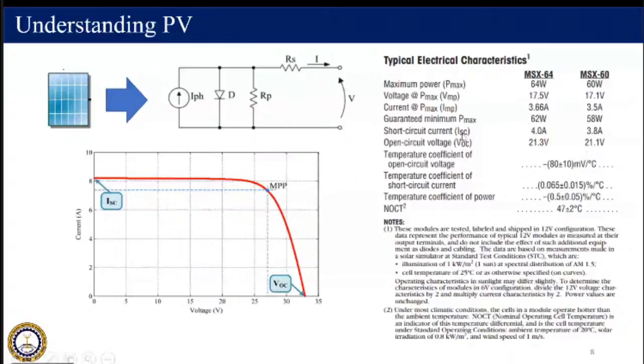So unlike traditional generators like a synchronous machine or a battery, PV has characteristics of both a constant current and a constant voltage source. Until a particular point called the maximum power point, the PV operates as a constant current source. Irrespective of the load you connect, it will try to inject a constant current, and the voltage depends on the value of the impedance you connect. But after the MPP, it almost maintains a constant voltage, and the current depends on the load. So it has characteristics of both. As you can see from this graph, till the point MPP, the current is constant. After this point, the voltage variation is very small, but the current variation is huge.